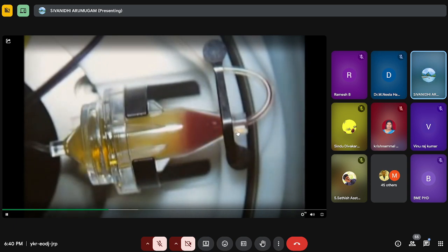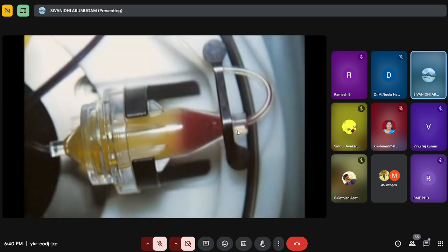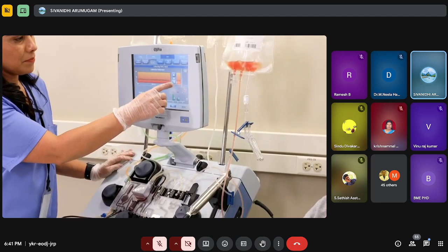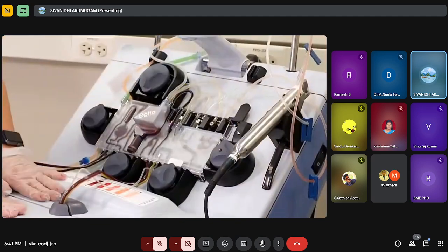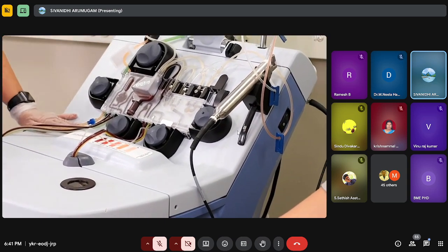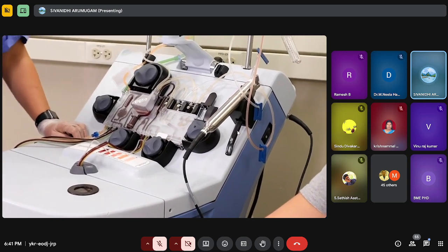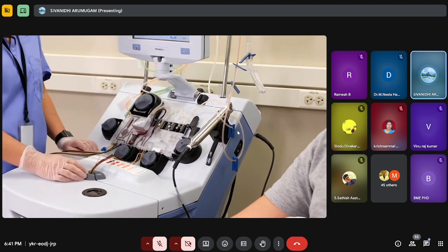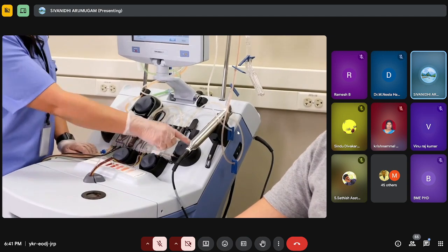The target cells are held in the chamber during a secondary separation step. The platelets are then pumped back to the patient. The system detects when the chamber is full of target cells and automatically moves into the collection phase. In the collection phase, these cells are pumped to the collection bag. The way collection phases are triggered can be tailored to the patient or procedure goals. After the cells have been flushed from the chamber, the system begins refilling the chamber. The system repeats these phases until the run target is achieved.